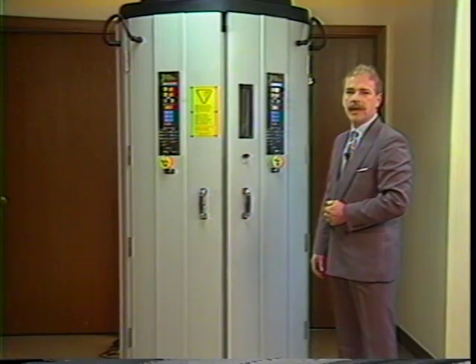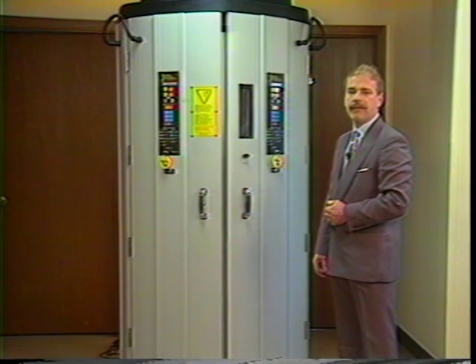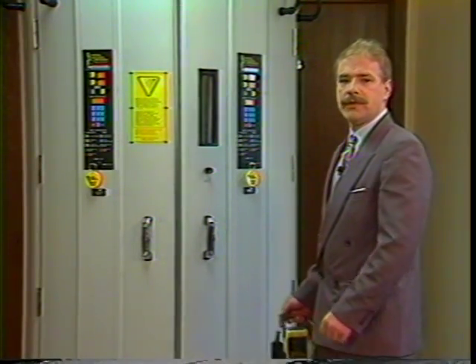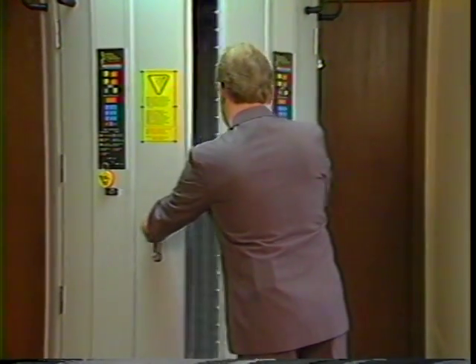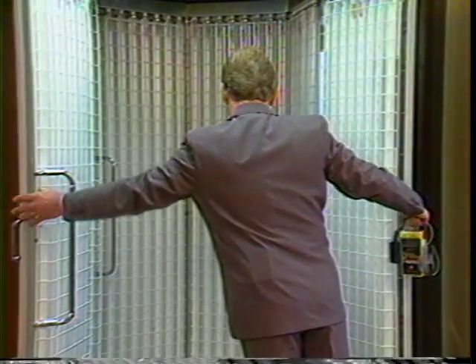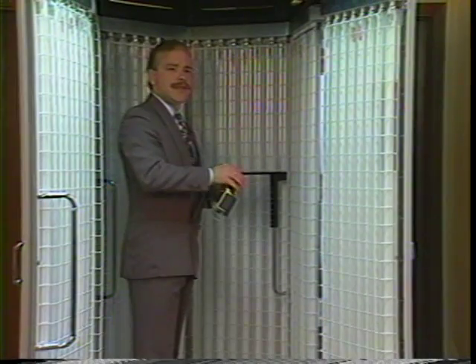The PhotoSense timer will automatically count the time down, shut the lamps off at the end of the 5-minute warm-up period. The PhotoSense timer will then emit 3 loud beeps as it reaches 0. Now you are ready to read the lamp output for the UVB lamps. Now open the doors to the HOUVA II unit. You will be placing the UVB metering probe in the center probe clip.